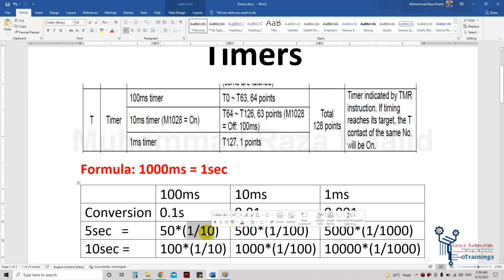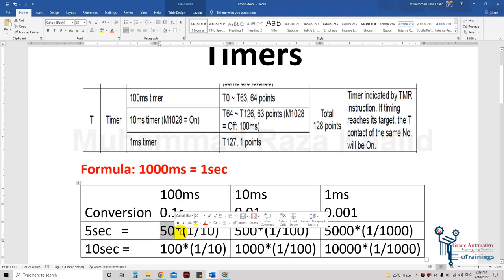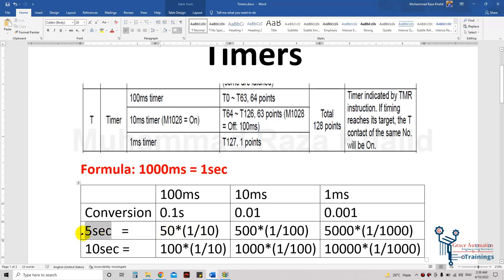So if I write 50 for the PV — the preset value — 50 multiplied by 1/10 gives 5. So to make this timer run for 5 seconds, we must give a preset value of 50.